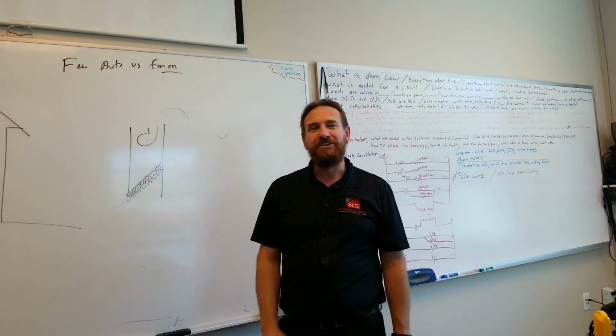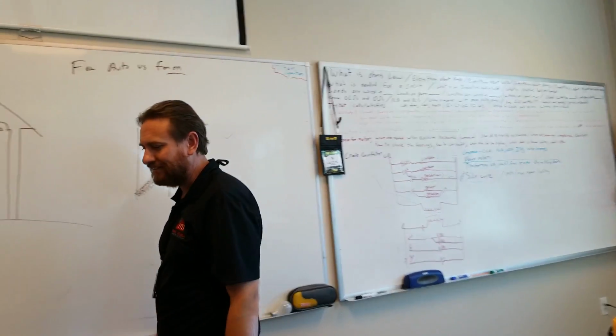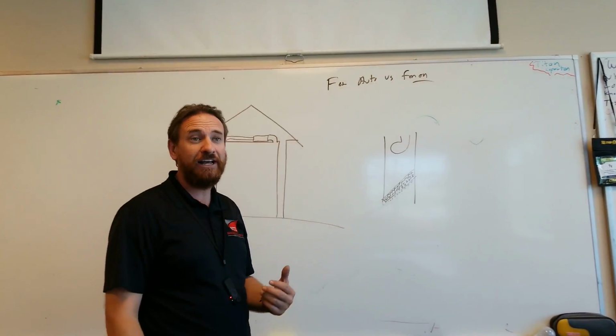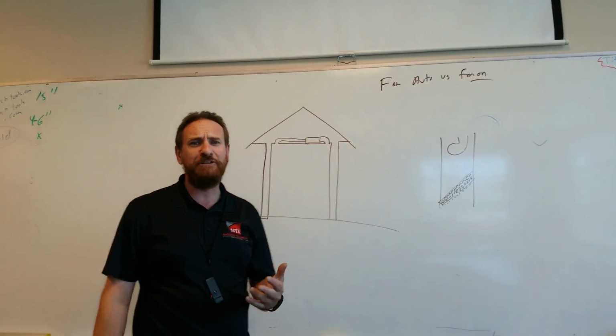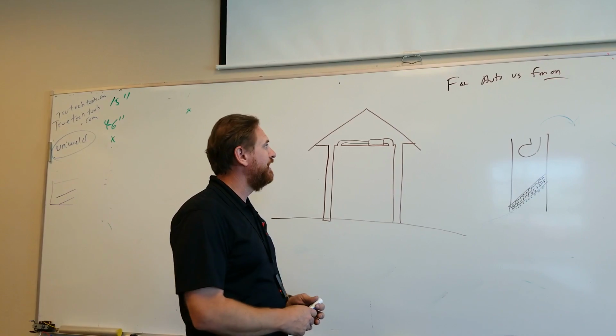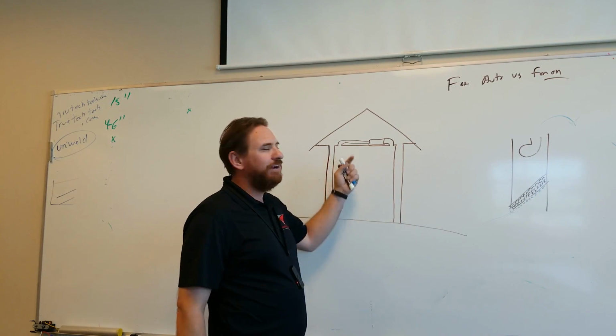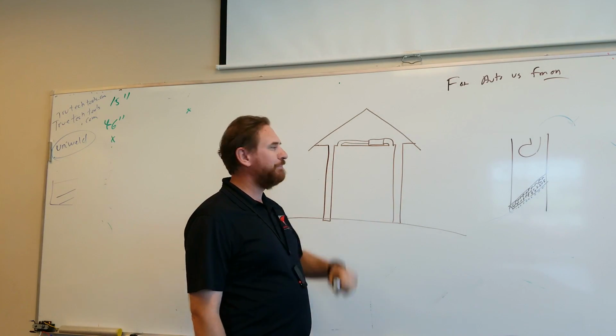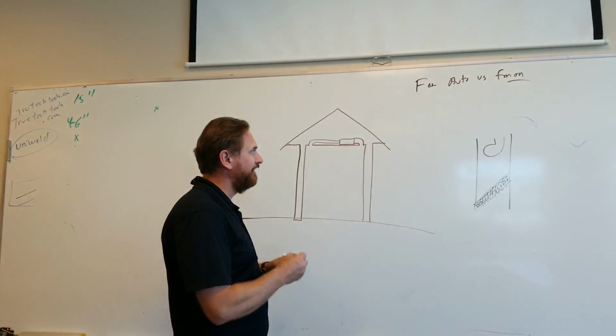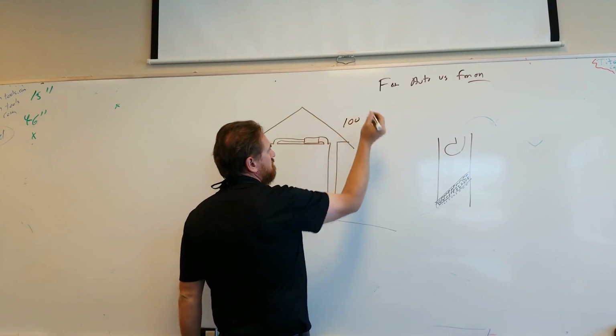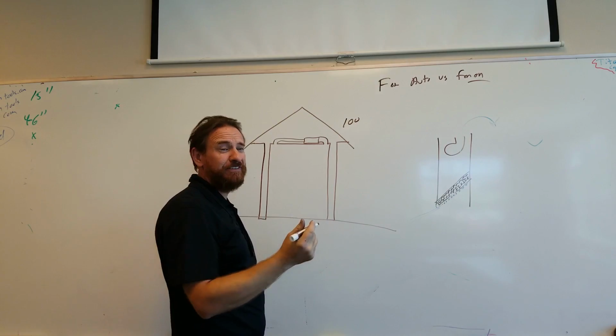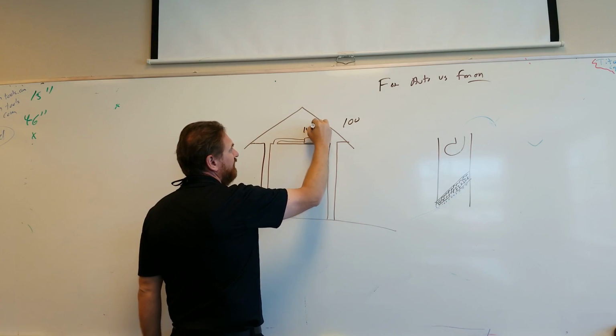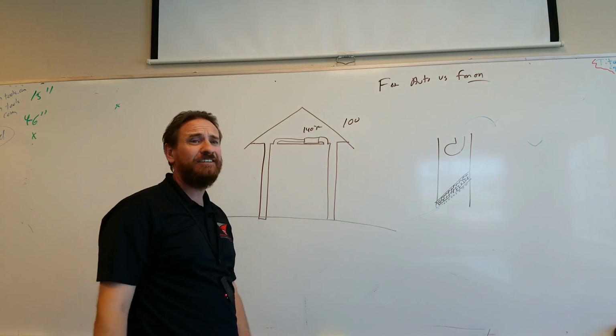But it really depends on also now your ductwork. So let's think about Las Vegas where it's very dry. There's no dehumidification we have to worry about because it's so dry here anyways. The ductwork, though, around Las Vegas and the unit itself is up in the attic. So let's say it's 100 degrees outside. You know, you're looking at about 140, maybe 150 in the attic. Let's say 140 degrees in the attic, which is significantly hot.